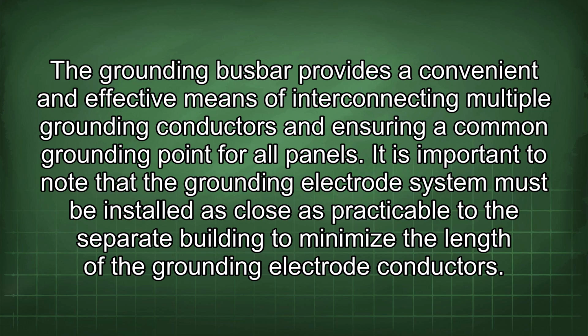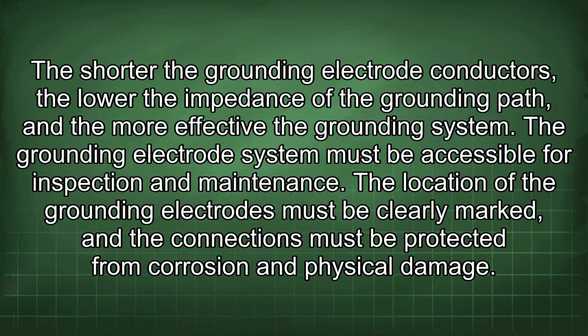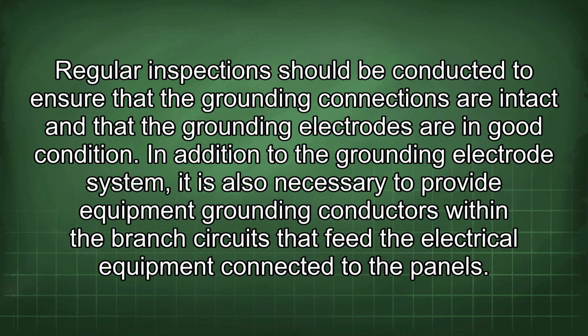The grounding busbar provides a convenient and effective means of interconnecting multiple grounding conductors and ensuring a common grounding point for all panels. It is important to note that the grounding electrode system must be installed as close as practicable to the separate building to minimize the length of the grounding electrode conductors. The shorter the grounding electrode conductors, the lower the impedance of the grounding path, and the more effective the grounding system. The grounding electrode system must be accessible for inspection and maintenance. The location of the grounding electrodes must be clearly marked, and the connections must be protected from corrosion and physical damage. Regular inspections should be conducted to ensure that the grounding connections are intact and that the grounding electrodes are in good condition.